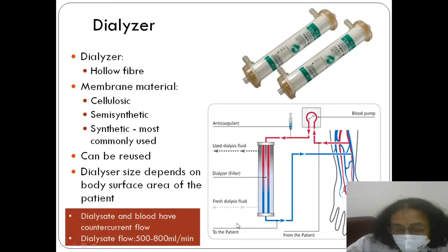So when we are dialyzing, we try to mimic the renal physiology. So the blood comes in, and from this top end it is passed through the dialyzer, where it is passed through these hollow fibers, while dialysis fluid is pushed in from the lower end. So the blood flow and the dialysate flow are in opposite directions. Counter current flow of the kidneys is mimicked over here to maintain the maximum concentration gradient. As I said earlier, the concentration gradient decides not only solute movement but also fluid movement. So to maintain the concentration gradient, there is a counter current flow. As we saw earlier, the blood flow is 300 ml per minute, while the dialysate flow will be around 500 to 800 ml per minute.